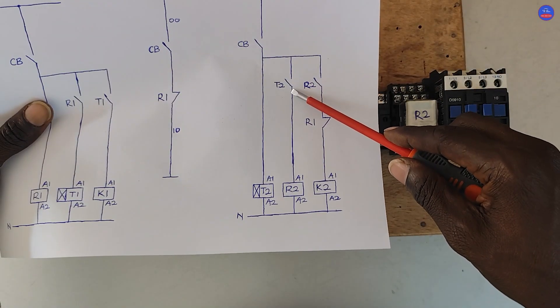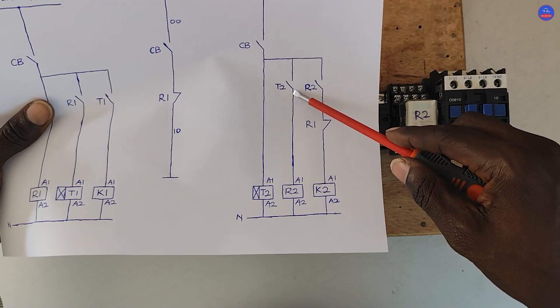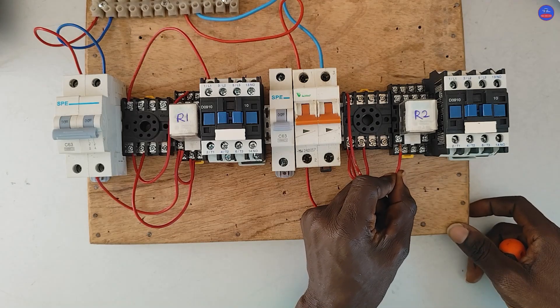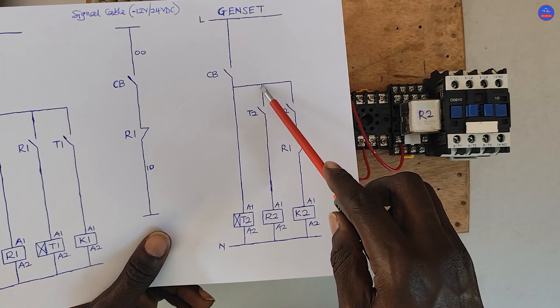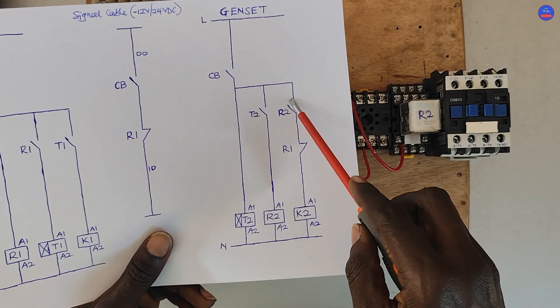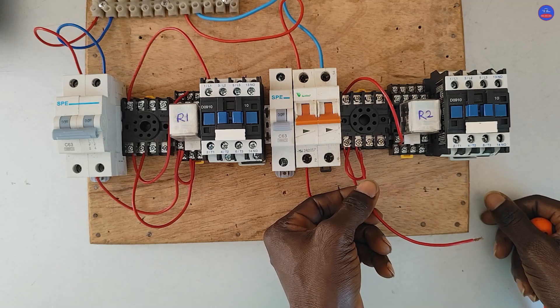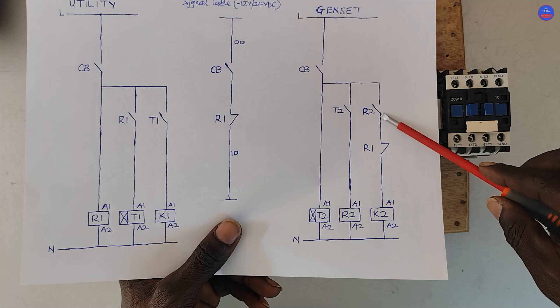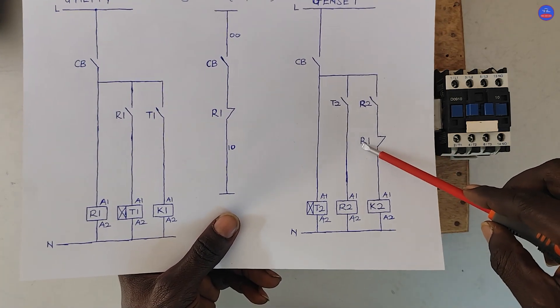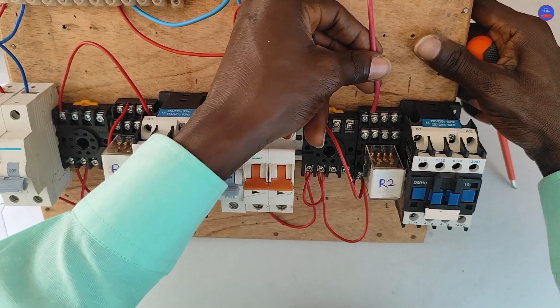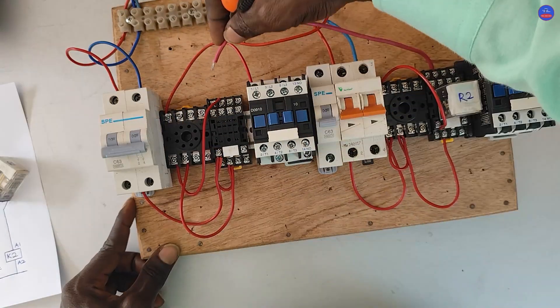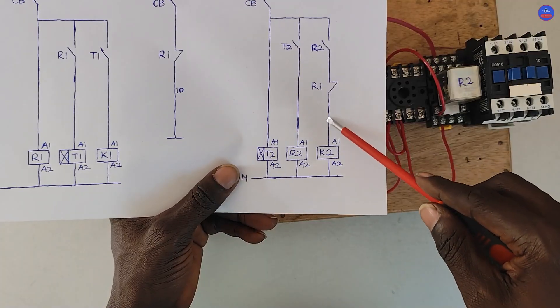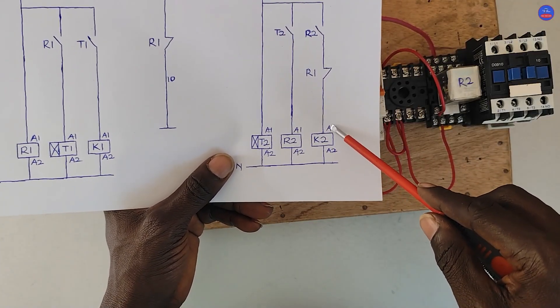From the other side of the open contact on the timer, which is terminal number 6, it goes to A1 on R2. We tap from the timer common contact to one side of the open contact on R2. From the other side of the open contact on R2, it goes to one side of the closed contact on R1. From the other side of that contact, it goes to terminal A1 on K2.